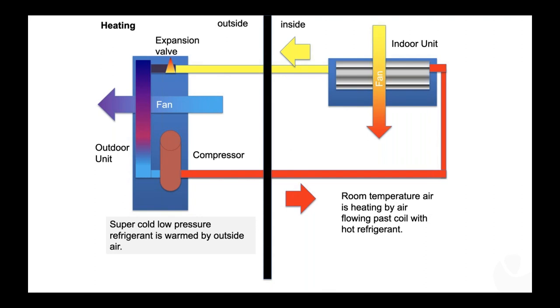Now, I know that when I was in high school and any time the topic of refrigeration cycles came up, that was my cue to fall asleep. So I made up my own little chart here to describe how the refrigeration cycle works for these mini splits. You can see the profile of an outdoor unit on the left-hand side and the indoor unit on the right-hand side. If we start at where the yellow arrow is, we have room temperature refrigerant under high pressure, around 400 PSI, in that ballpark, traveling to the expansion valve, which is the triangle on the left-hand side top.